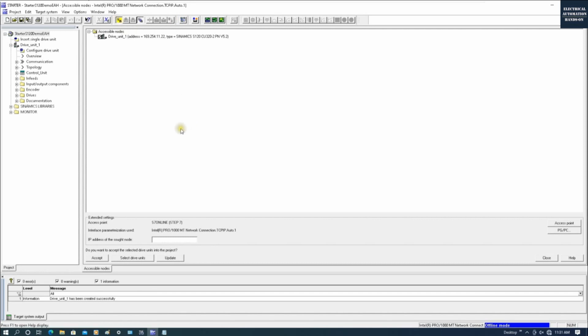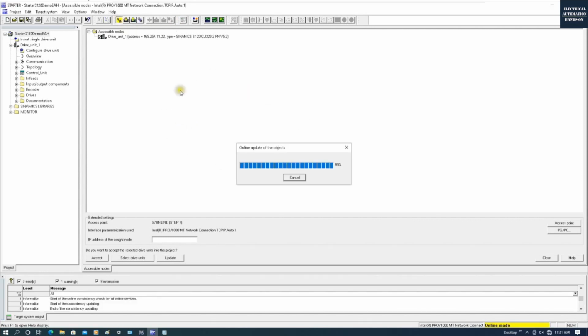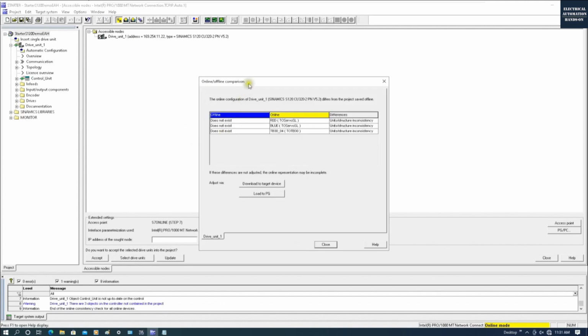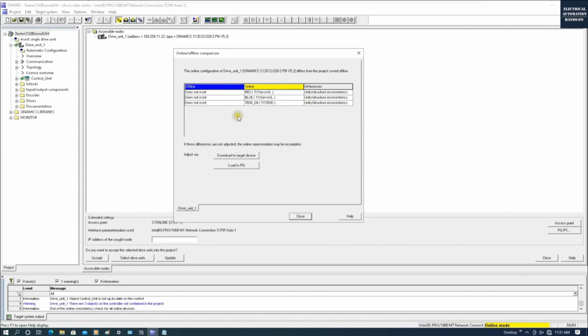The first time we click this online, the software will tell us whether our offline configuration and online configuration match. Definitely, this hardware came from others, so something has already been configured inside. So with this button, download to target, if something is already configured, you can click this button to directly override the online configuration.